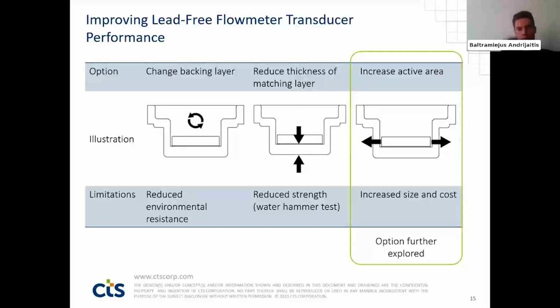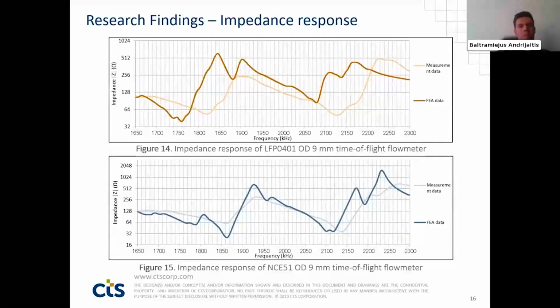So for further investigation, we chose to increase the active layer area from the used outer diameter 7 to outer diameter 9. And further, the same process of assembly, measurements, and finite element analysis was performed to get the investigated changes. More graphs. On the lead-free graphs, we can notice lower overall impedance values.